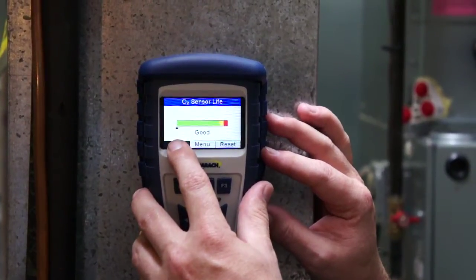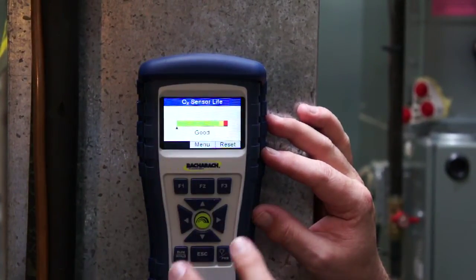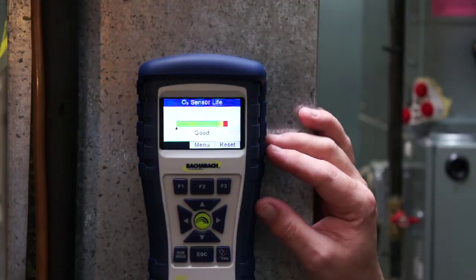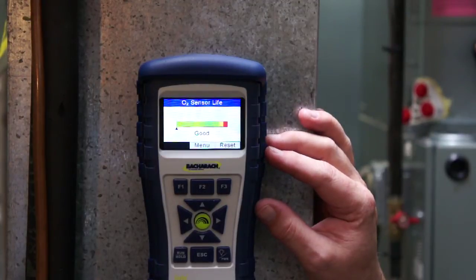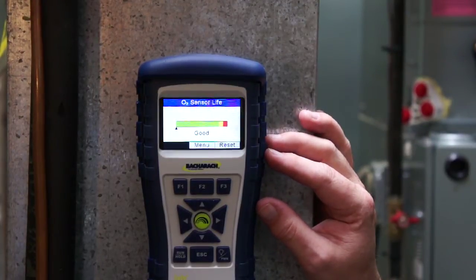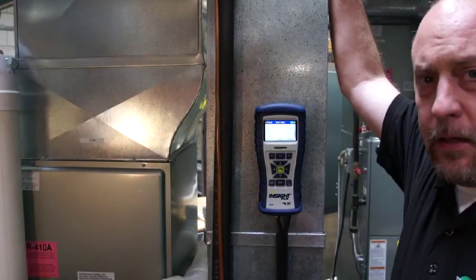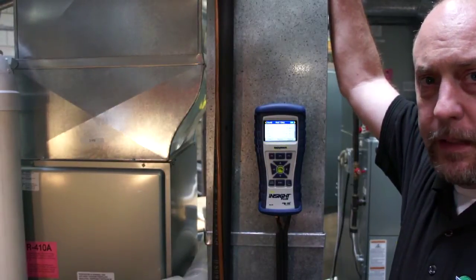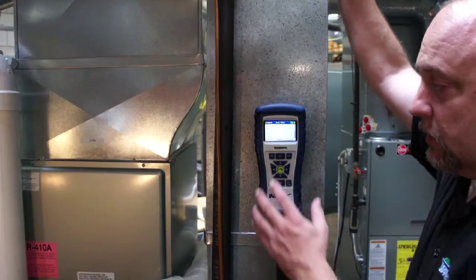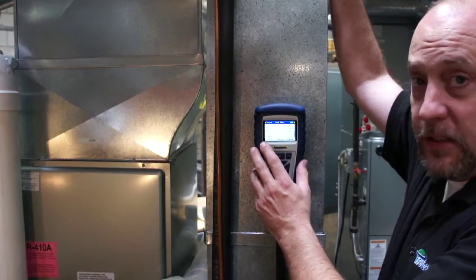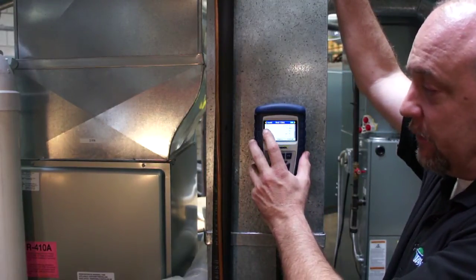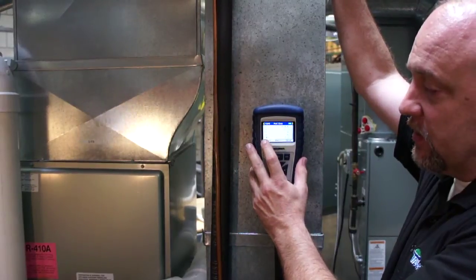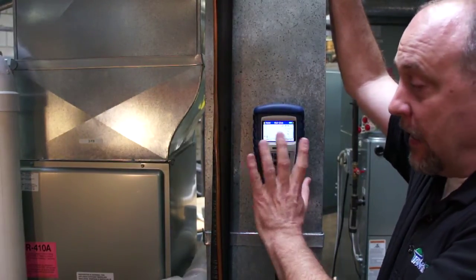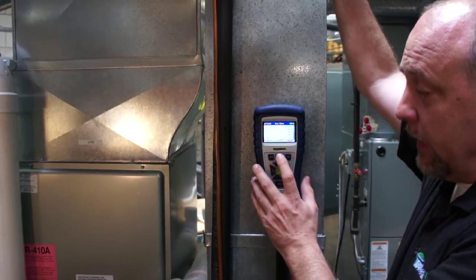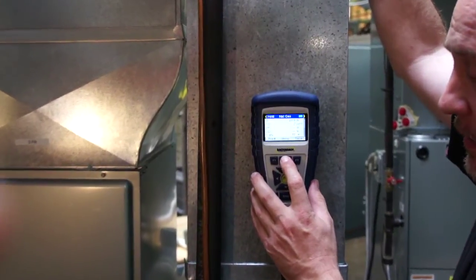good here because it's a brand new analyzer. A lot of things I can look at, configure exactly the way you want them. A lot of depth to the menu structures on this instrument. Not only are the user display and the units all configurable, we can also configure the order that we want things to show in. In this case, it comes factory set for O2, CO, efficiency, CO2, and the stack temperature. But I can go in and change that to make it set up the way that I want it to look. So in this case here, I go to the menu.